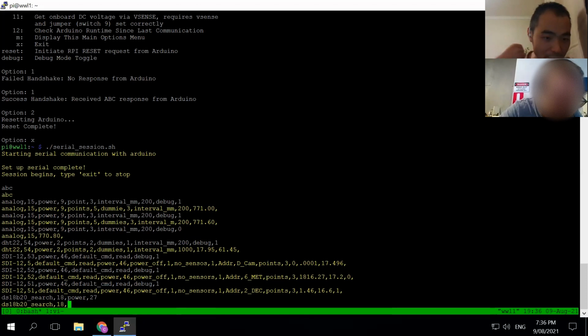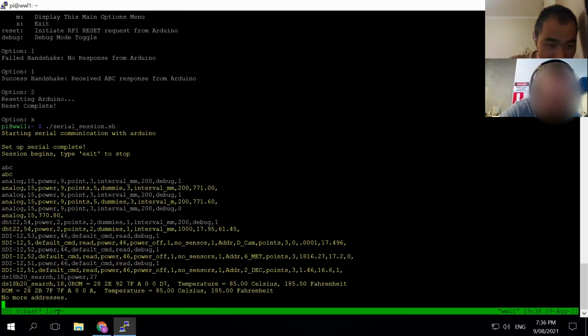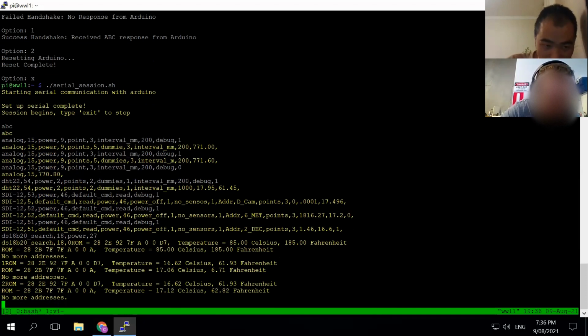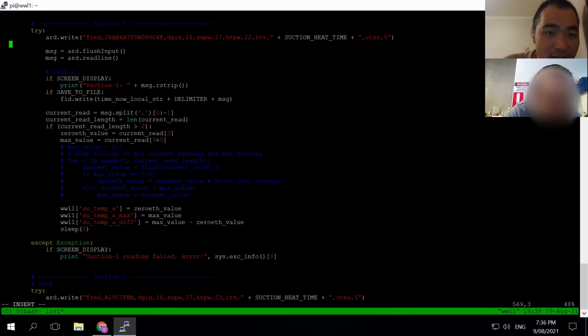So basically, when I push that command, this tells you there are two sensors in those digital ports, which is correct. And then when you find out the sensor ID, you need to tie that sensor with a specific heating element, because the sensor has two functions. One is to heat the sensor. The second is to measure the temperature. Which is the reason why, when you look at the command here, you've got a sensor ID, digital in, sensor power, and heating power. Heating power, exactly.